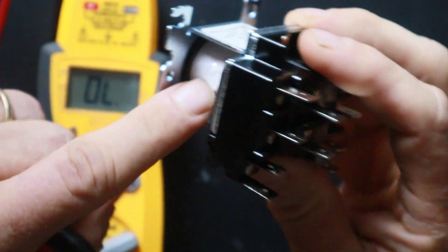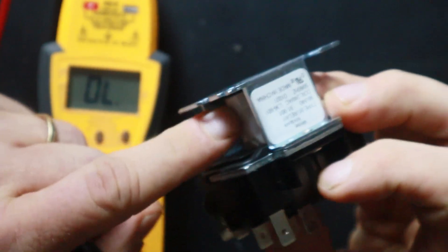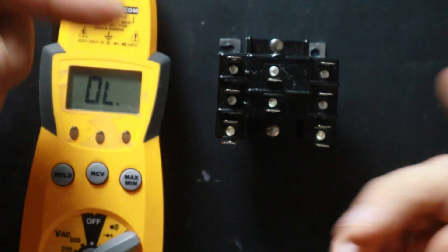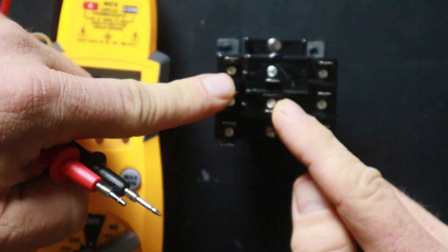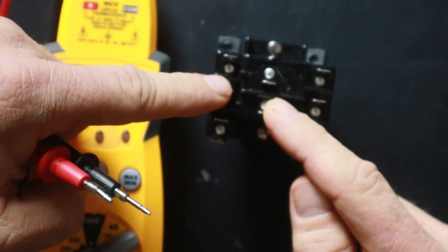So let's wrap up this video by talking about diagnosing these relays. There's a lot of questions out there and people always asking about how many ohms they should be reading on these relays when they test them with a multimeter. Now, this is going to be very manufacturer specific. It's going to be very specific to manufacturers. So it's really going to be a value you have to look up based on the relay that you have. But generally speaking, you have to know the difference between a coil and a contact. So our coil is the winding that you will find inside these relays. Sometimes you can see them, sometimes you can't, but it's a winding that goes around and around. So there's going to be a lot more resistance on there than say a contact, which is just both ends of the actual switch itself. So the switch is just a connection between one terminal and the other, and it's not a lot of resistance there.